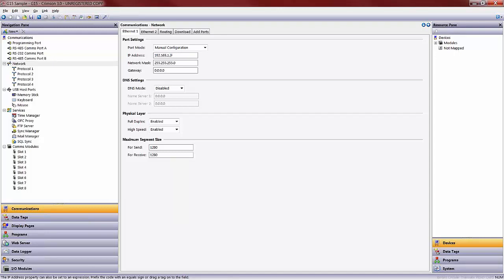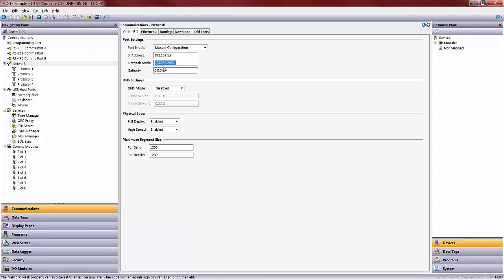We will assume that the GE IP controller is at a 192.168.1.2 address, so we can plug the Red Lion at a 192.168.1.3 address, something different and available on the network. I am going to leave my network mask set to 255.255.255.0, and in this case I am not working with nor do I have a gateway, but if I did I would plug that in here.